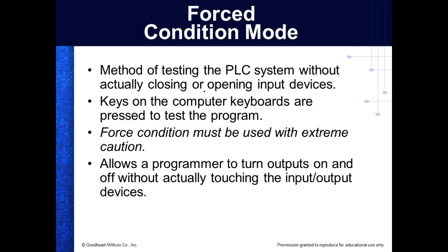Forcing outputs, guys, you have to really be careful on that because those are going to be running things, right? So before you force an output, you need to make sure you know exactly what the consequences are going to be. I think I told you about the guy at US Steel that got pinched up in the top of number 8 blast furnace because they forced the wrong contact. They locked out where they were working, but they didn't lock out the bottom one.